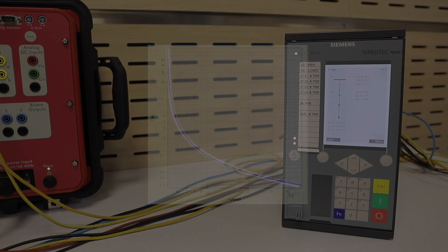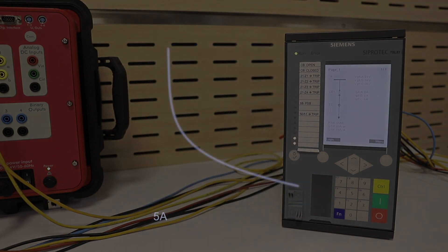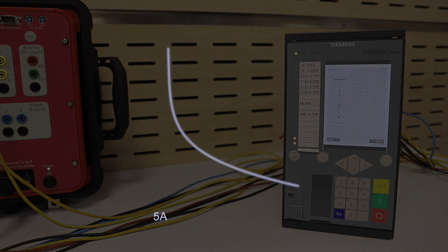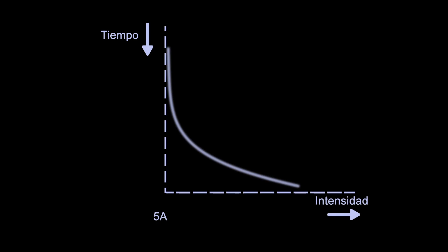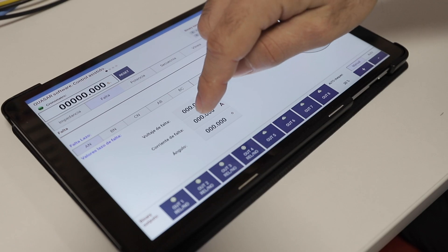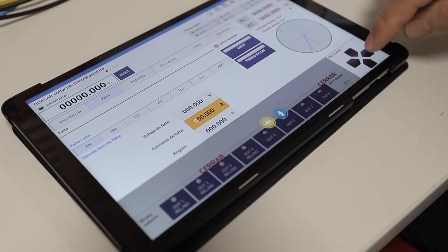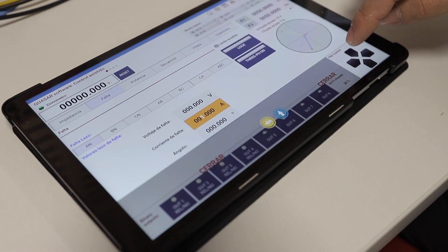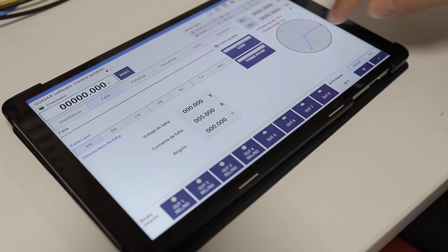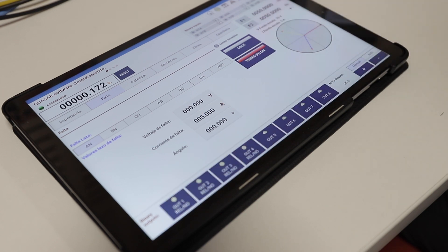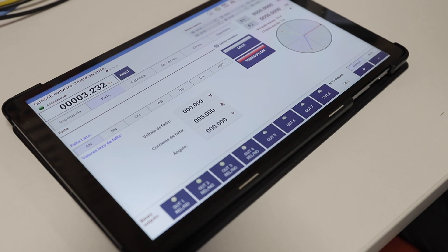From this point on, the larger the injected current, the shorter the operation time. This behavior is known as inverse time overcurrent protection. When fault current is detected, the relay starts its internal chronometer. If the current persists beyond the associated time in the curve, the relay will operate and will turn this LED on.